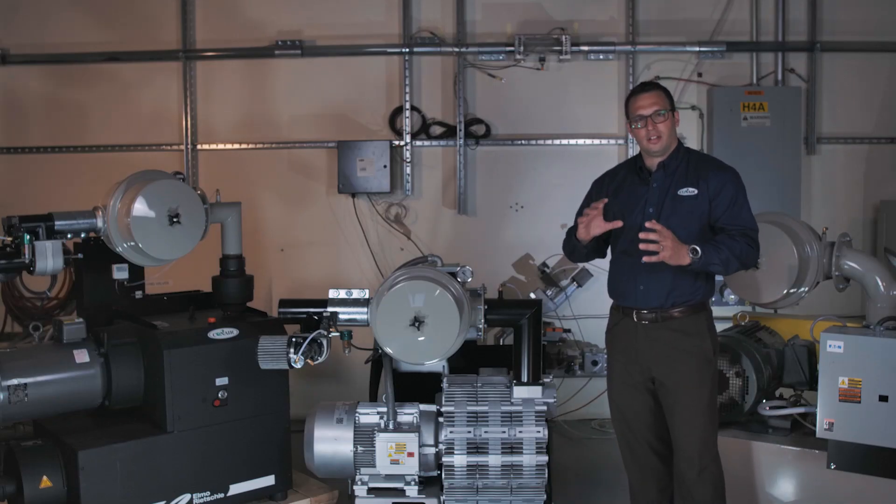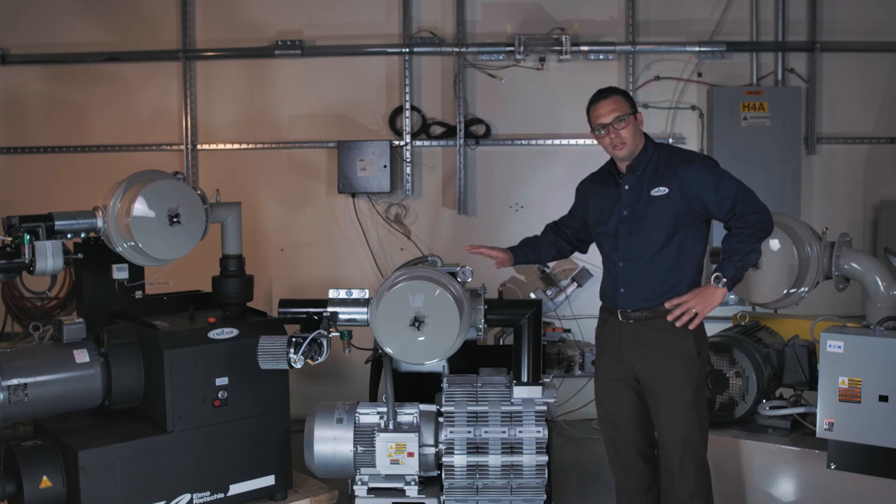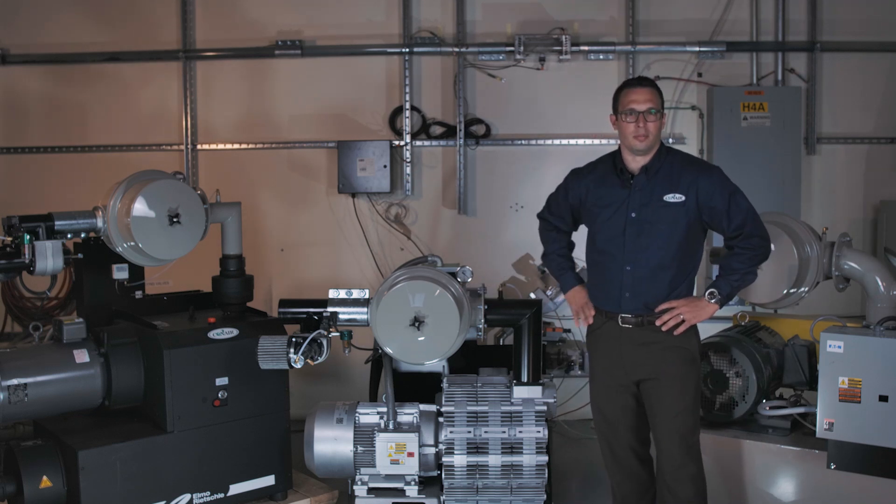The HRG is also capable of having a VFD on it, and that VFD is going to allow us not only to dial in certain CFMs based on certain applications if you're in dilute phase, but that VFD is also required when operating in dense phase conveying. The HRG pump, just like on the pump curve I showed between the PD, the LDP, and the HRG with respect to throughput and distance, it also fits a perfect window with respect to dense phase applications where 90% of dense phase applications now can use the HRG pump compared to previously having to go with the LDP pump family.